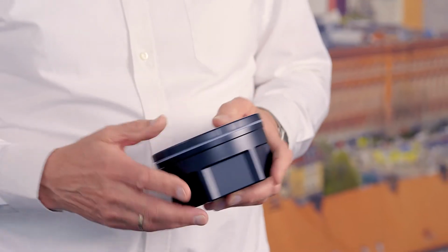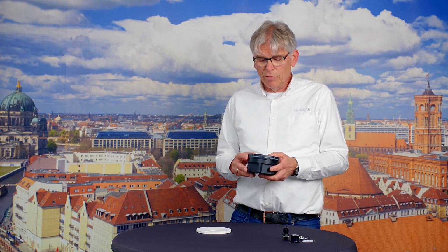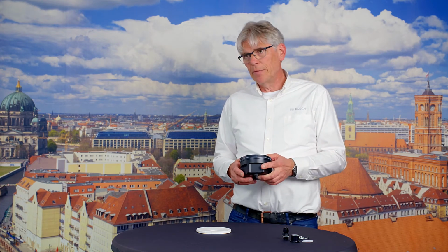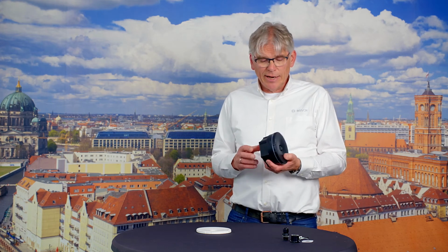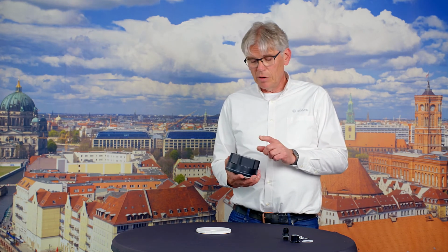and that can be done by measuring the noise level via a device like this, that operates per zone, and you can have a maximum of 4 of these devices to cover very large zones. The ambient noise sensor is connected via the OMNEO network, so it is securely connected via IP, and only level information is transported on the network, no audio streams, so there is no risk of eavesdropping, and the network bandwidth occupied is relatively small. The device itself is also powered from the network via PoE, Power over Ethernet.